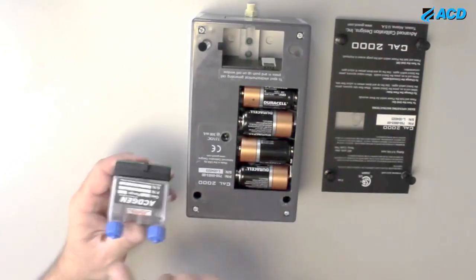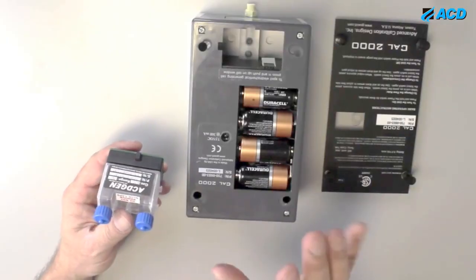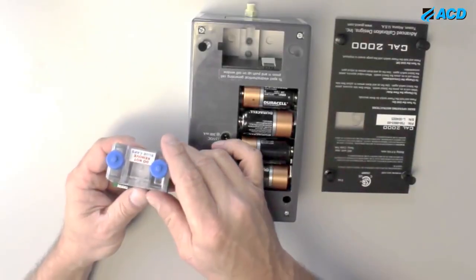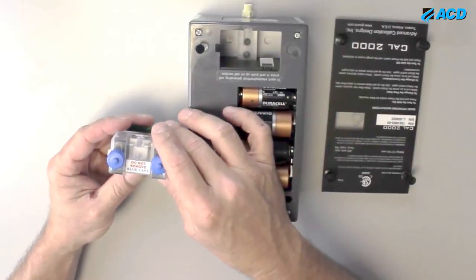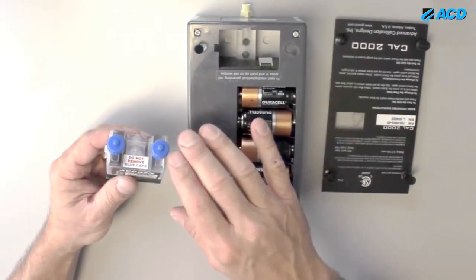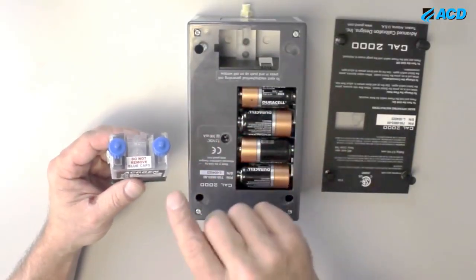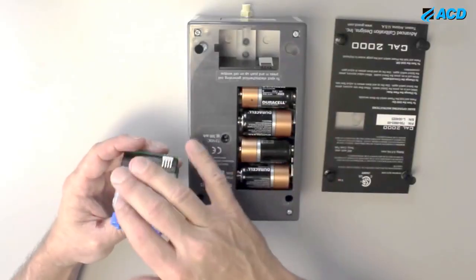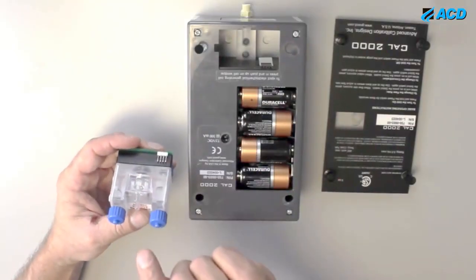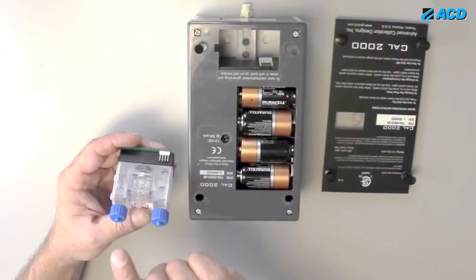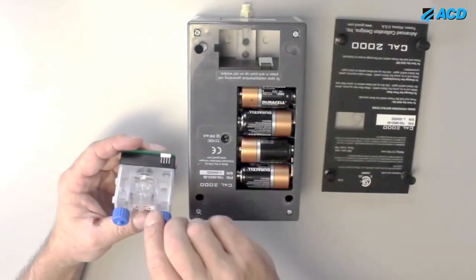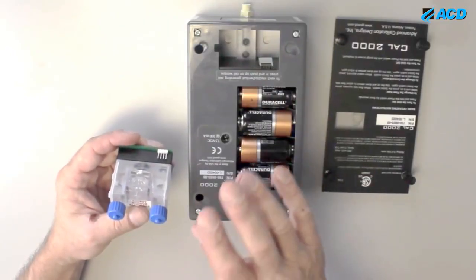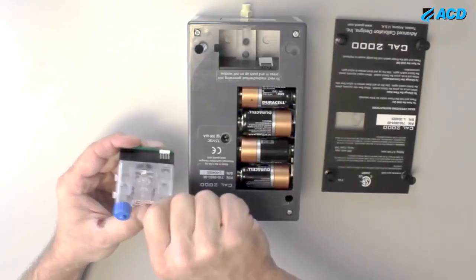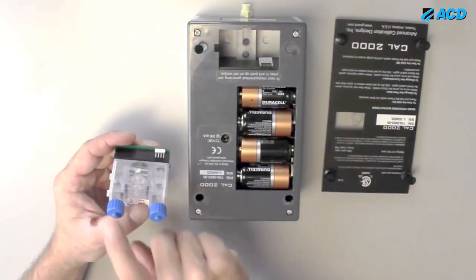Now the source has 2 caps on top of it, but you never need to remove them. There's a little sign there that says do not remove the caps, but in general, they're only there because sometimes in real dry atmospheres, the electrolyte inside here will sort of dry up and you can take those 2 off and add distilled water. There are O-ring seals at the top again, so generally, you're never going to take them off. If you do, to add water to it, then put the caps on tight and you're ready to go.